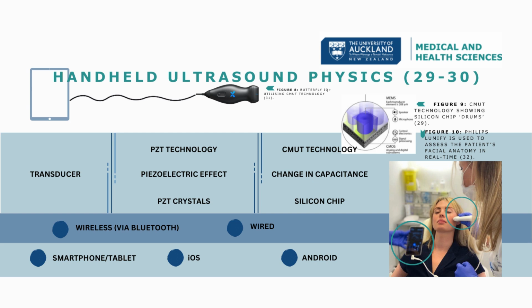In handheld ultrasound devices, the transducer contains an active element technology, which is either made of piezoelectric crystals similar to the conventional ultrasound transducers, or a silicon chip. PZT crystals mechanically vibrate when voltages are applied to produce sound waves, and vice versa. A voltage is produced when it receives sound waves. This is the piezoelectric effect.